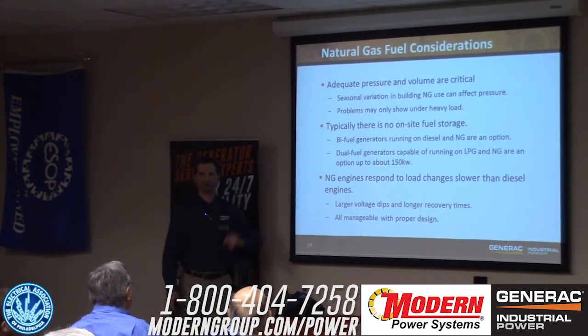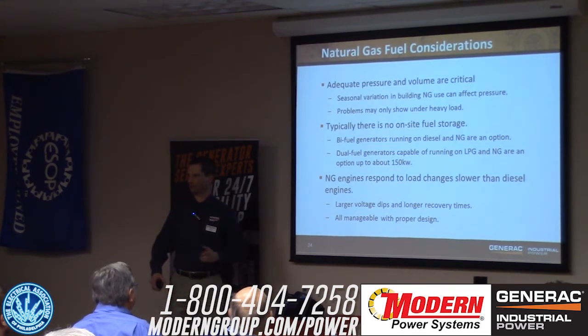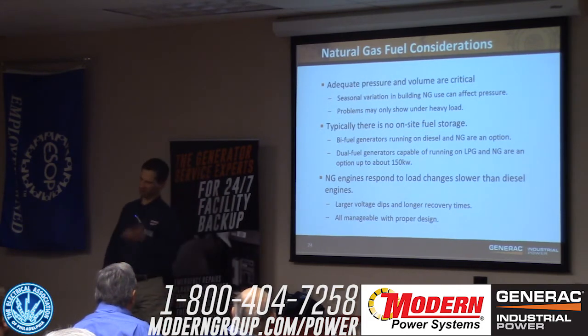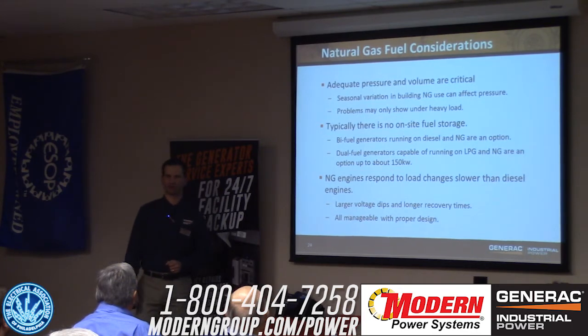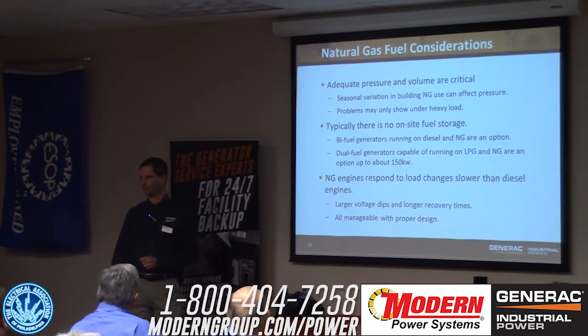You're only going to see those issues under heavy load. If you do an unloaded exercise or run a genset with light load, it's going to be fine for the most part, even if it's not getting awesome gas flow. But if it doesn't have good gas pressure and adequate flow, it will let you know very quickly that it's not getting enough gas.